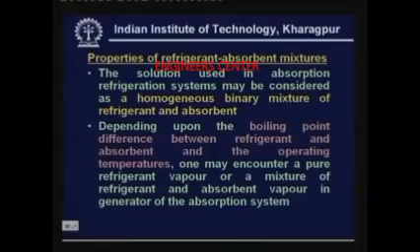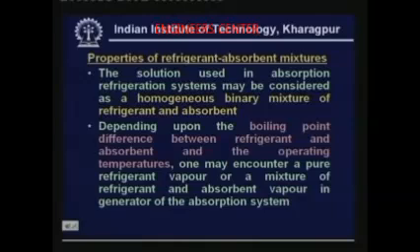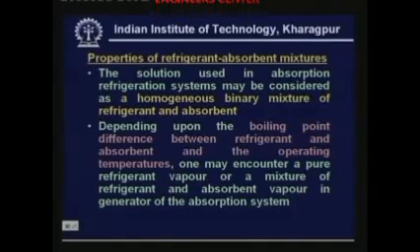Depending upon the boiling point difference between the refrigerant and absorbent and the operating temperatures, one may encounter a pure refrigerant vapor or a mixture of refrigerant and absorbent vapor in the generator of the absorption system. While describing the simple vapor absorption system, in the generator you supply heat at high temperature and refrigerant vapor is generated, which then goes to the condenser. But in actual systems, depending upon the boiling point temperature difference, in addition to the refrigerant vapor you may also have some vapor of the absorbent in the generator.